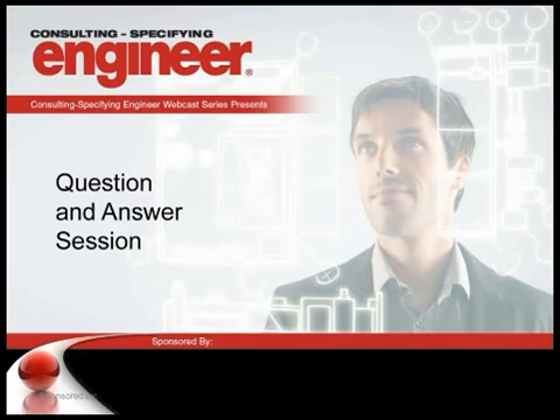So I think it's a question that you need to ask your local code authorities when you start designing the systems. Yeah, and I would agree with Dean. And it would be somewhat related and separate when you're talking about overlapping neutrals versus the syncing of the phases when you do a make versus break. So it would actually be two separate. One you might make for 5 seconds or some short amount of time. In other situations, just the neutral.